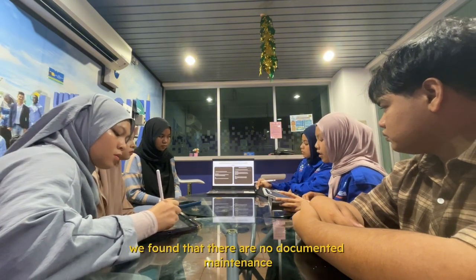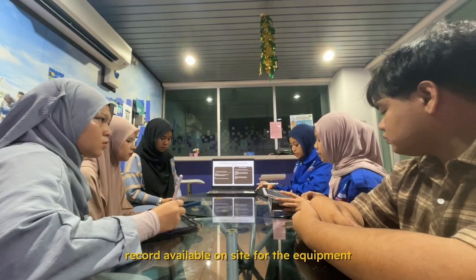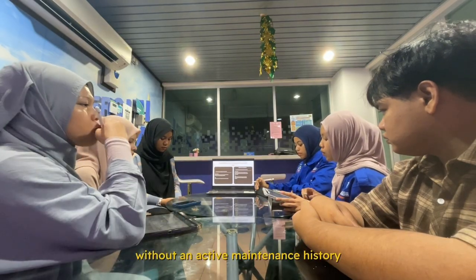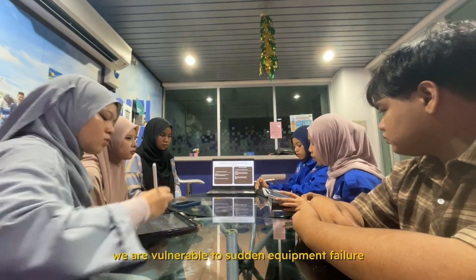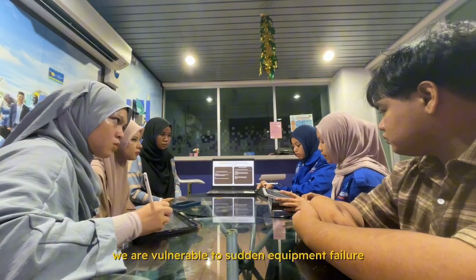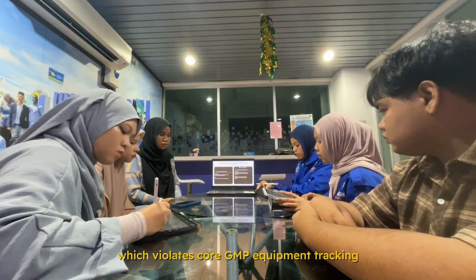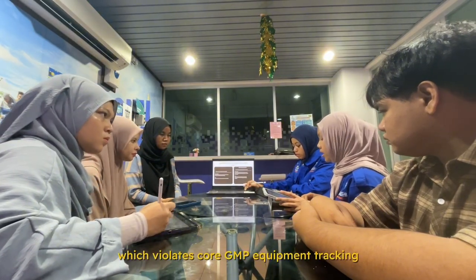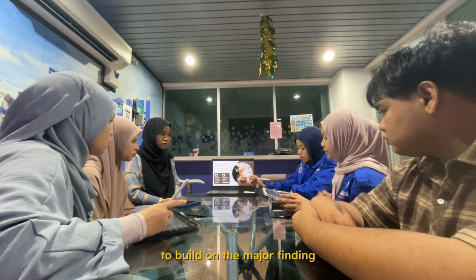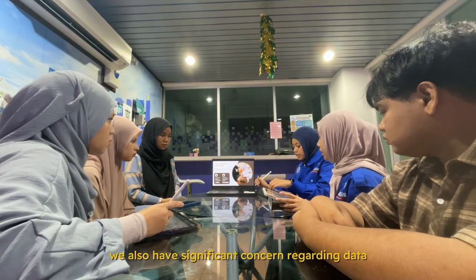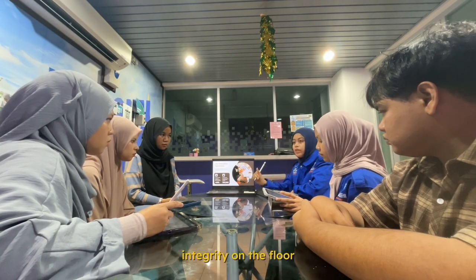Second, we found that there are no documented maintenance records available on site for the equipment. Without an active maintenance history, we are vulnerable to sudden equipment failure and mechanical drift, which violates core GMP equipment tracking.